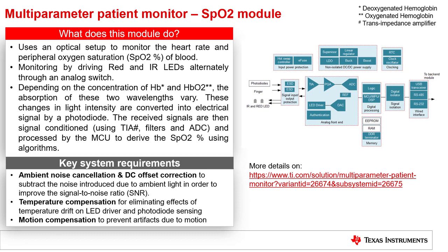The key system requirements for the SpO2 module are: ambient noise cancellation and DC offset correction, to subtract noise introduced due to ambient light in order to improve SNR; temperature compensation, for eliminating effects of temperature drift on LED driver and photodiode sensing; motion compensation, to prevent artifacts due to motion; small form factor, for easy adaptation to portable applications; and low power consumption, to maximize battery life while driving multiple LEDs, such as RED or infrared.